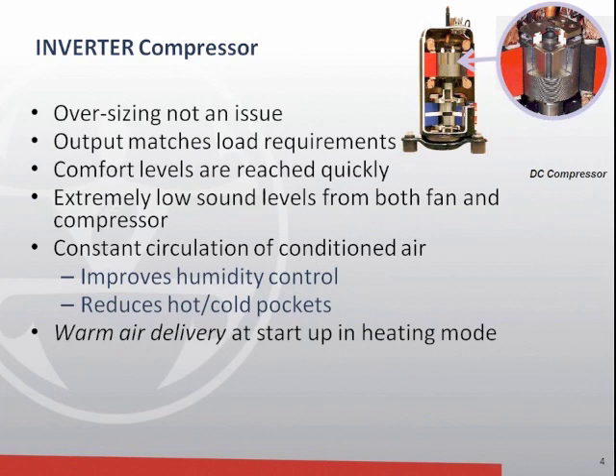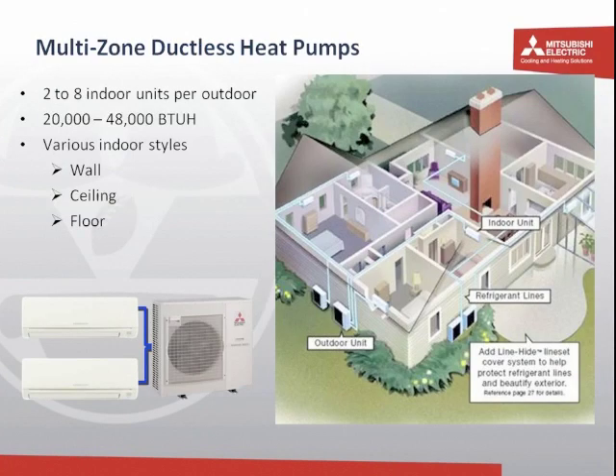So these inverters are a core of the system. They're a part of what makes all of the systems we're going to talk about work in all their different configurations. So stepping from that simple one-to-one outdoor unit, indoor unit configuration, the first generation of improvements I want to talk about is the multi-zone ductless heat pump. These systems are capable of tying as many as 8 indoor units into a single outdoor condensing unit.